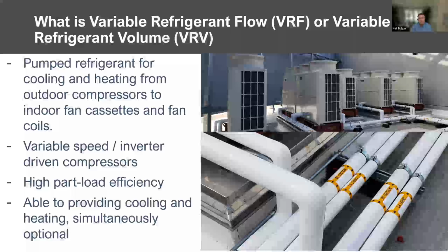That results in really good efficiencies at part load operations. You can run those compressors at part load speed. You have these outdoor compressors and coils that have lots of surface area, and so VRF can optimize how the refrigerant system is running. It can take advantage of those large surface areas, change the pressures and the temperatures of the refrigerant that it's compressing and pumping, and therefore squeeze some efficiency out of these systems. We'll look at some inside pictures in a second. They can work in heating and cooling. You can definitely buy these where they only do heating or cooling, but a lot of projects use the ones that can do simultaneous heating and cooling, using both the hot refrigerant and the cold refrigerant to heat and cool different rooms in a building. That's another functionality of VRF that's really attractive. It gives a lot of flexibility to buildings.